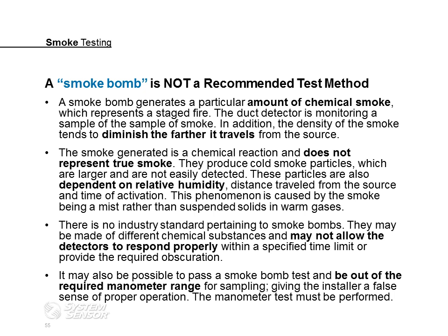Another problem with smoke bombs is that there is no industry standard pertaining to them and how they're manufactured. They may be made of different chemical substances and may not allow the detectors to respond properly within the specified time limit or provide the required obscuration. It may also be possible to pass a smoke bomb test and be out of the required manometer range for sampling, giving the installer a false sense of proper operation. The manometer test must be performed. We have to perform that test, but we absolutely do not recommend smoke bombs for testing. If it's required to have smoke introduced to the head, then we suggest that you introduce canned smoke to the smoke detector head and do not use smoke bombs.